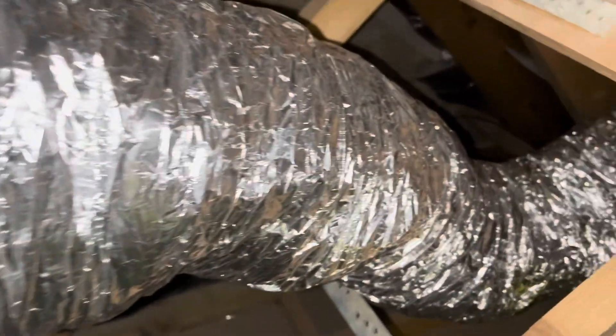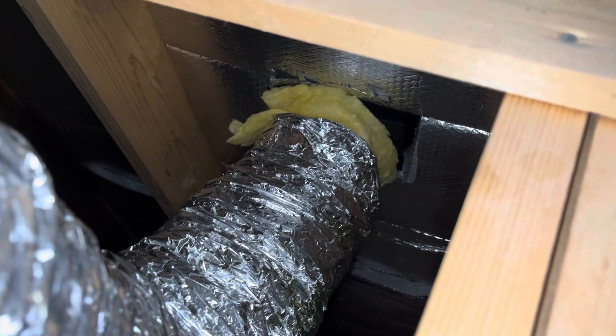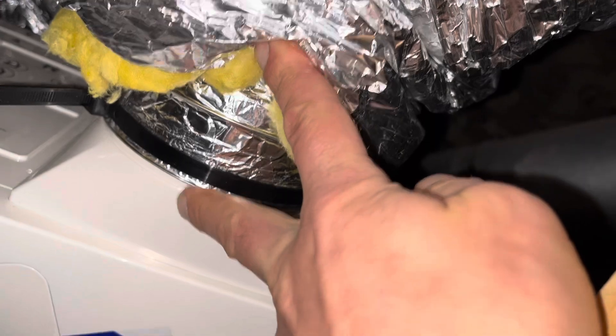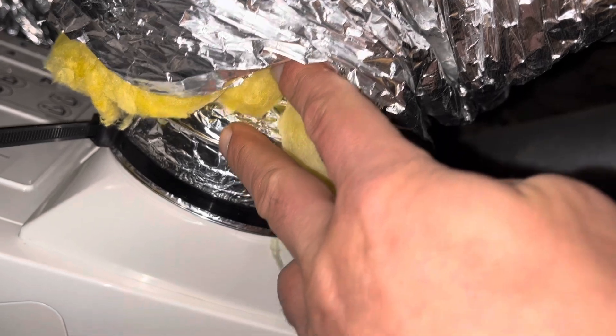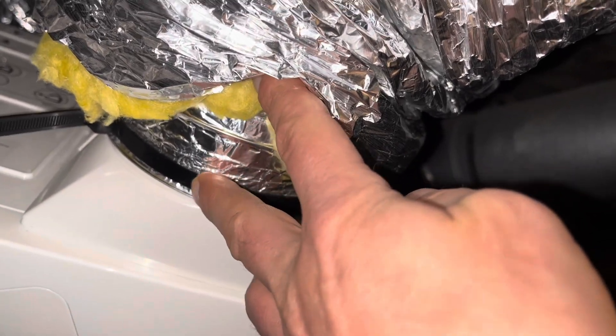I've attached this ducting to the outside now. That rectangular end fitted in there and goes to the outside of the roof. I've also attached all the other ducting to the top of the MVHR unit. The pipes coming out are called 125mm spigots, and this is 125mm ducting so it slips over quite nicely. I've used a zip tie to secure them so no air escapes.